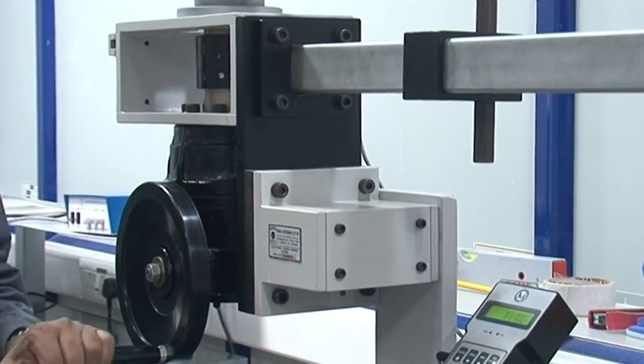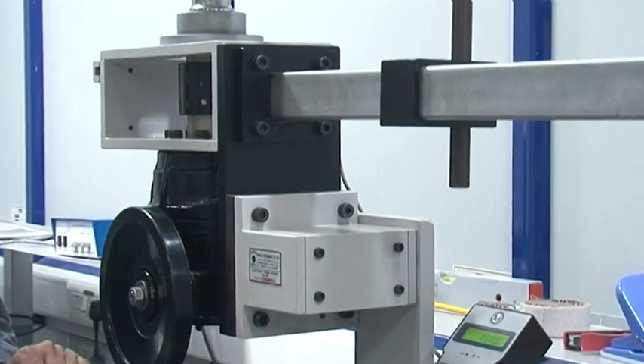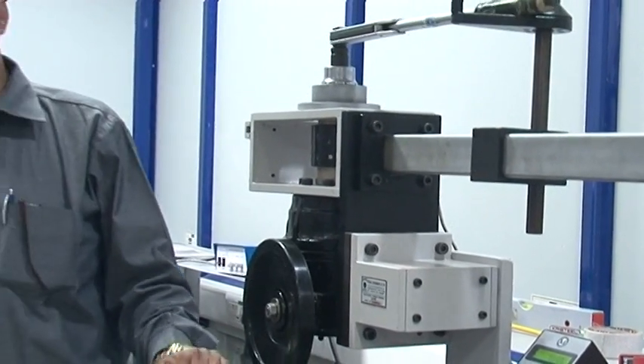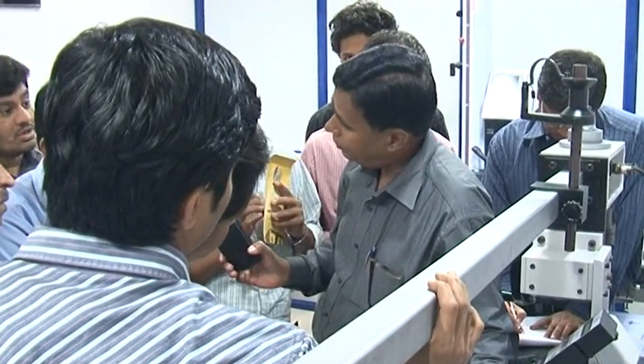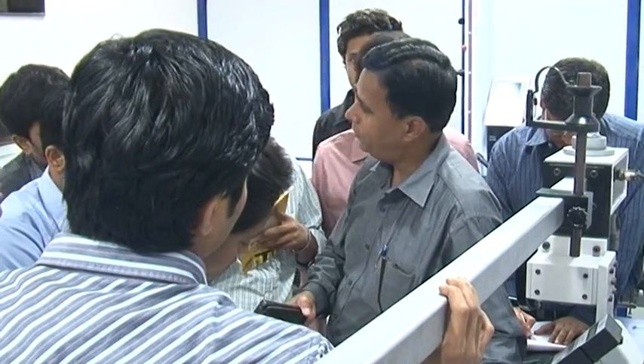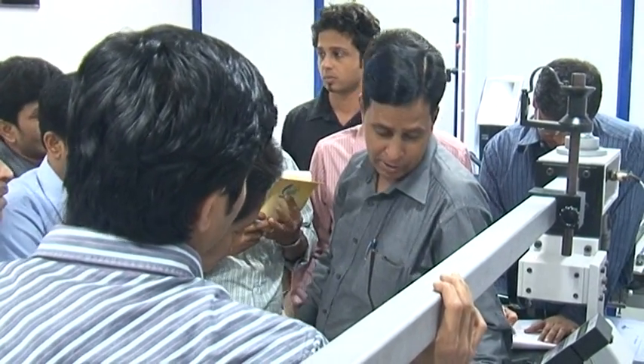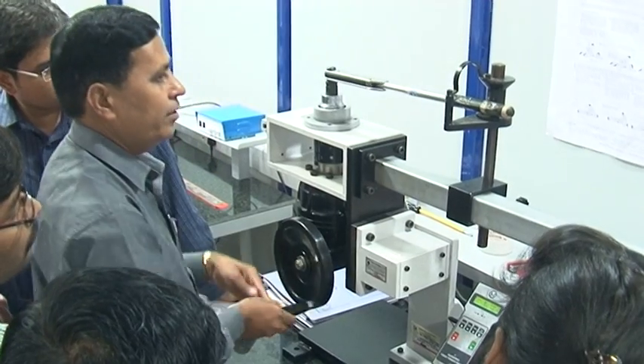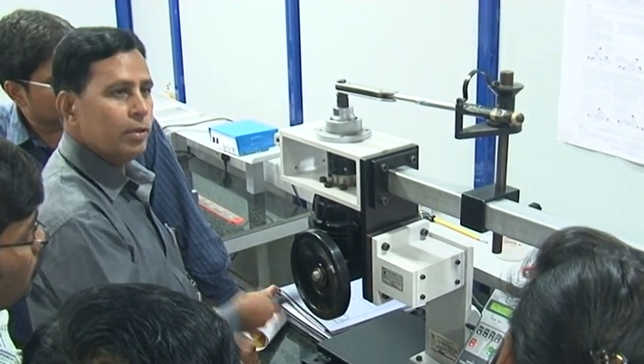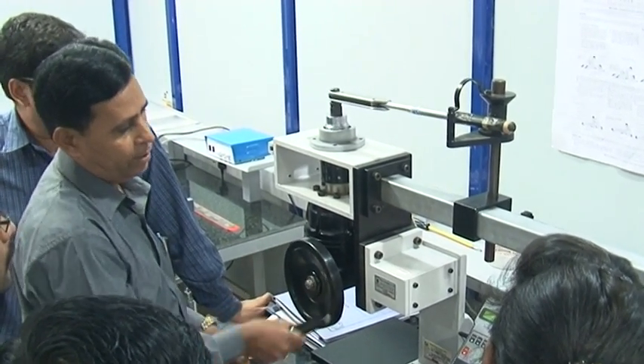We can calibrate adjustable type, dial type and digital type torque wrenches on this tester. As per IS standard, first we have to take a reading at 20%, then 60% and finally at 100% of range. After mounting the torque wrench on the tester, torque is generated by rotating a wheel, and at a certain stage the torque wrench clicks and the peak point value is noted by the DRO.